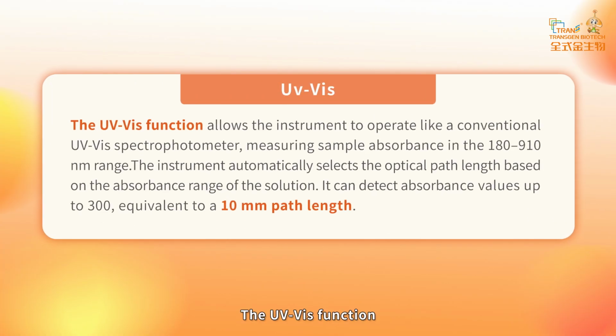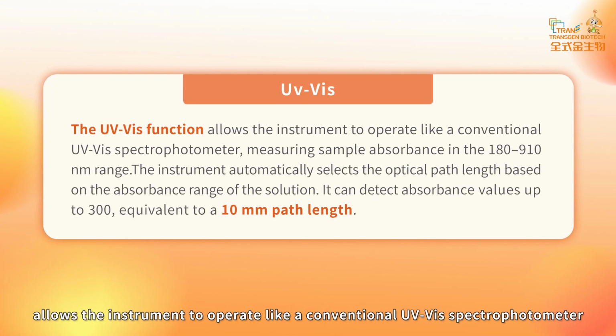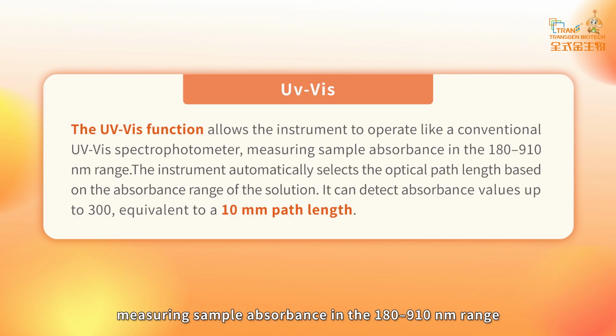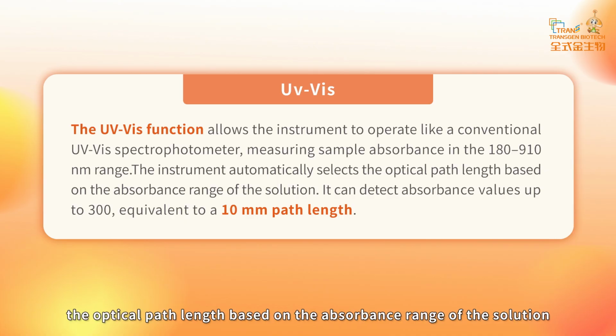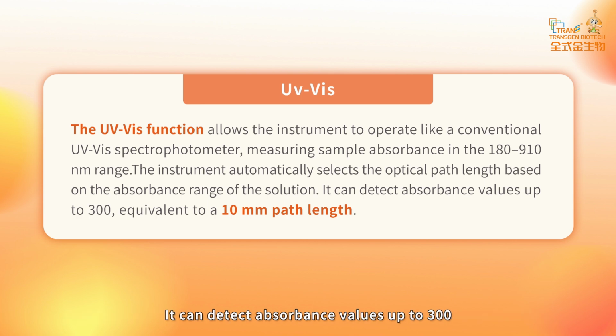The UV-Vis function allows the instrument to operate like a conventional UV-Vis spectrophotometer, measuring the sample absorbance in the 180 to 910 nanometer range. The instrument automatically selects the optical path length based on the absorbance range of the solution. It can detect absorbance values up to 300, equivalent to a 10 millimeter path length.